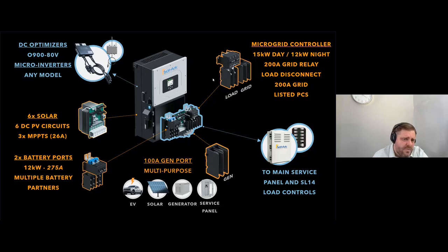The solar side for DC coupled solar for Sol Ark follows a 'let's do it large, make our components robust and have fewer problems' mentality. We have 3 MPPTs in the residential line, and the commercial line has 4. But these MPPTs are what I call full-sized MPPTs, meaning every MPPT circuit is the same amperage. All 3 MPPTs are 26 amps each, and that means you can parallel solar circuits onto them, accommodating up to 6 solar circuits.